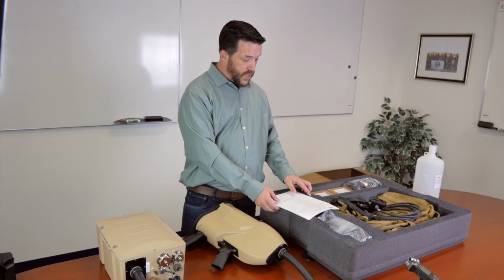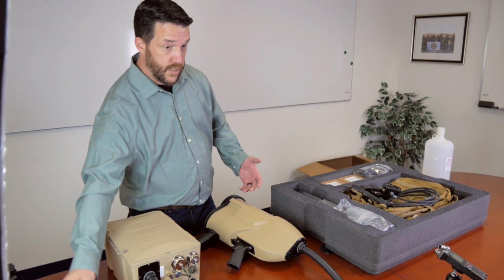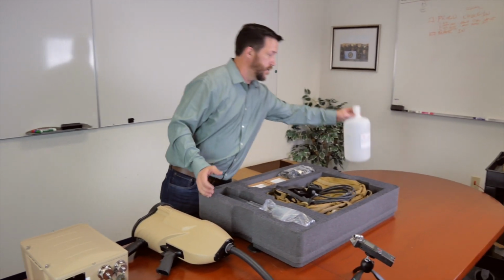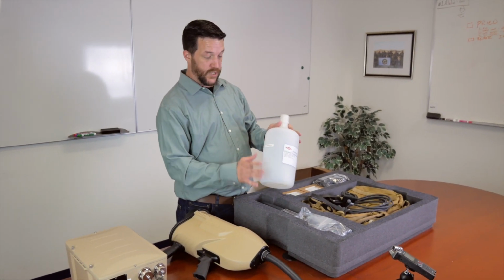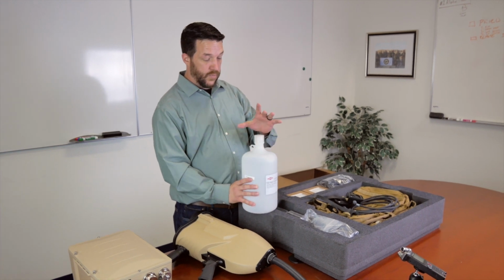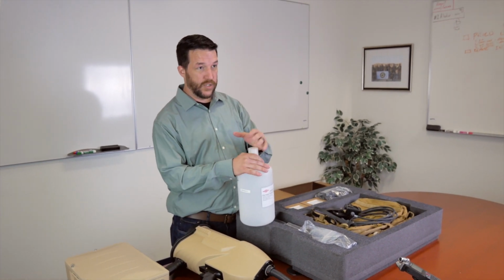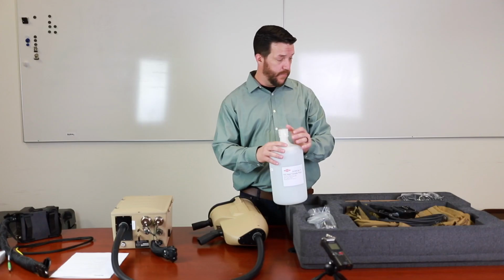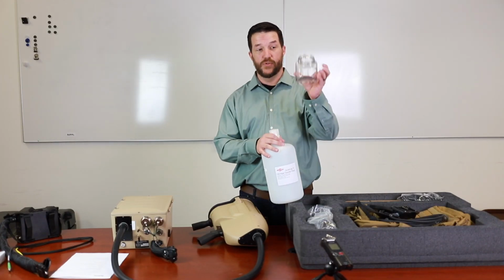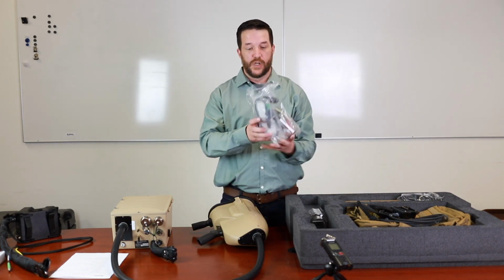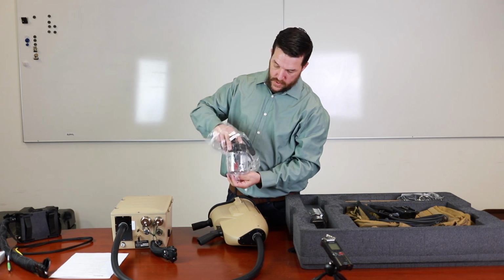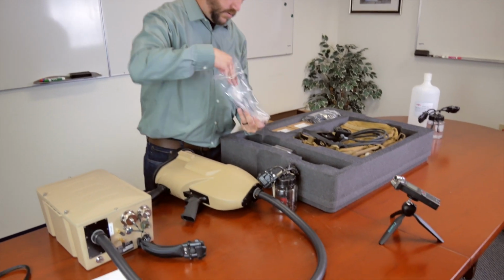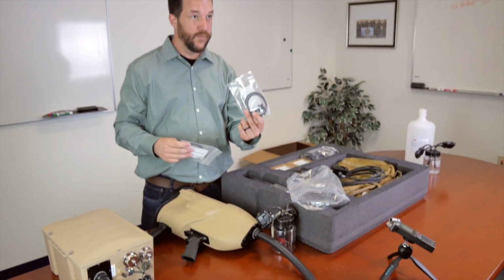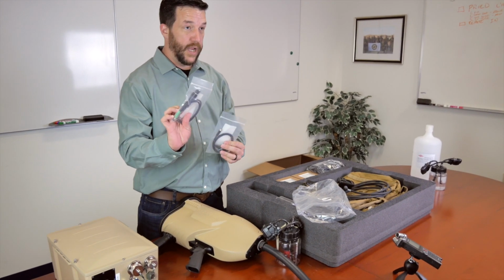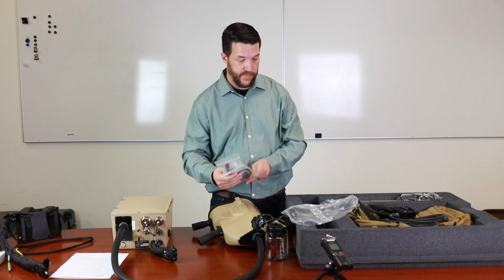Right. Third step of what we're going to do is actually fill our system. So using our glycol mixture, which is part of our consumables kit, we'll use an 80-20 mixture. So 80% water, 20% of the glycol mixture, and you will use your fill kit bottle to do this. So, using our fill kit, take out our fill bottle, and both the power for the chiller and our comms cable, which will turn it on and off.